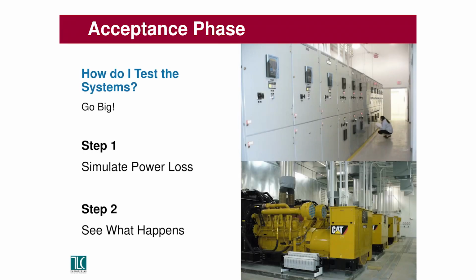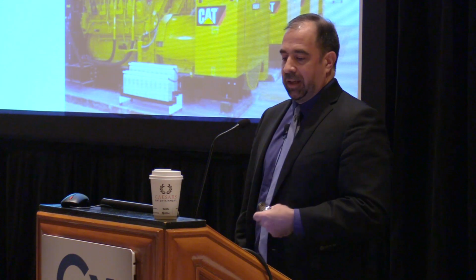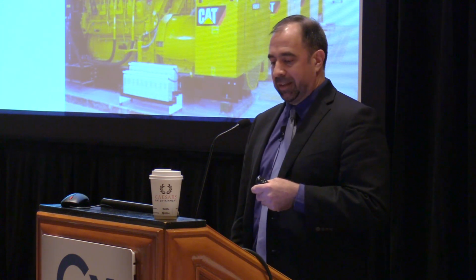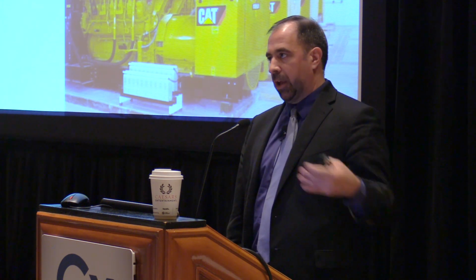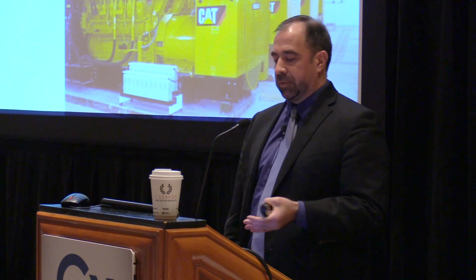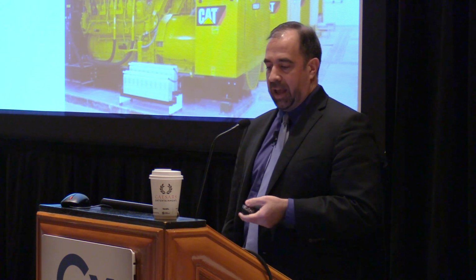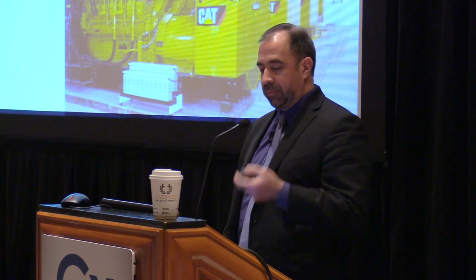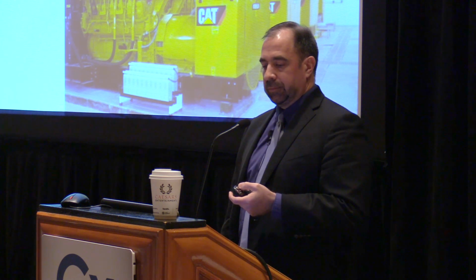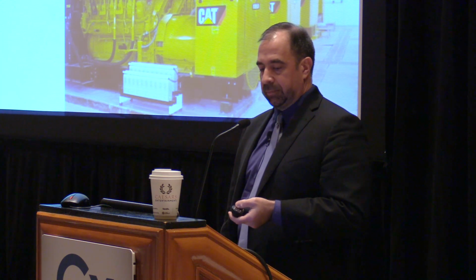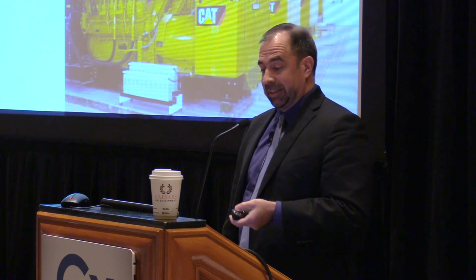And then my favorite part is we turn stuff off and see what happens. This is more fun in a brand new facility where you can literally just kill the main. But in existing hospitals, you can't just go turn this stuff off, even in part, so we're usually testing one transfer switch at a time. We simulate normal power loss to that one transfer switch, make sure it transfers, and everything else that's supposed to happen happens. Every project's different, and we write those tests to meet the project requirements, but that's essentially it - we turn it off and see what happens.